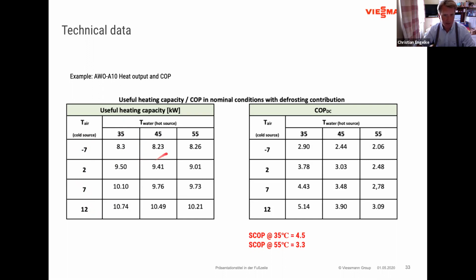So you can see that if you use the worst case scenario for a heat pump, running it at 55 degrees at -7, that's obviously the highest temperature you want, the output is 8.3 kilowatt. But if you run the air source heat pump at 12 degrees outside temperature and low temperature, then you will see that the output is increasing by more than 20%. And that's the classic behavior you have with every air source heat pump.